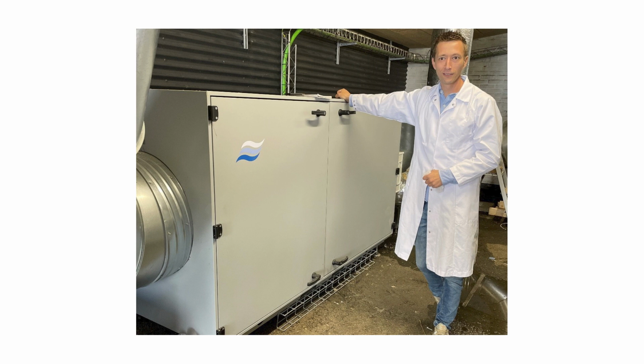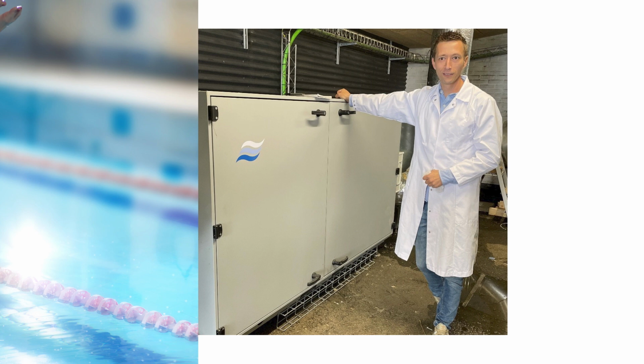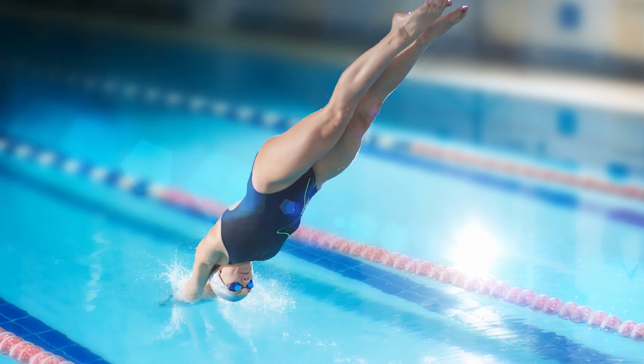Yeah, indeed. It's a good point. Any internal sources of water must then be factored in as well as the external sources. For instance, if the area is a swimming pool, then the internal load will be significant. The pool volume, the water temperature, and the hours of operation will help calculate the amount of evaporation. Now, people also give off water, and we do so at varying levels depending on our level of activity. Again, a quality dehumidifier manufacturer will be able to help with these calculations. But to do so, some specific details like the ones I've mentioned need to be determined.